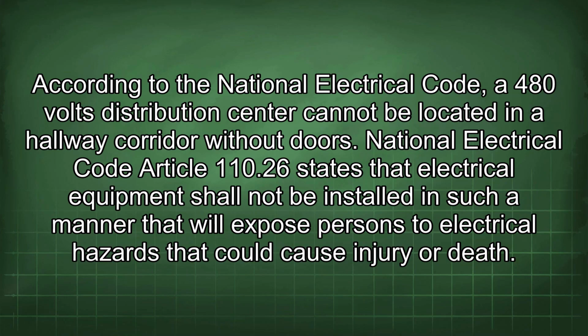According to the National Electrical Code, a 480 volts distribution center cannot be located in a hallway corridor without doors. National Electrical Code Article 110.26 states that electrical equipment shall not be installed in such a manner that will expose persons to electrical hazards that could cause injury or death.